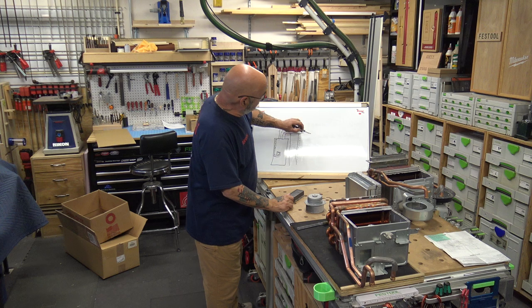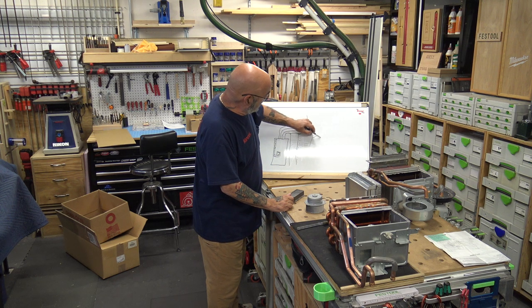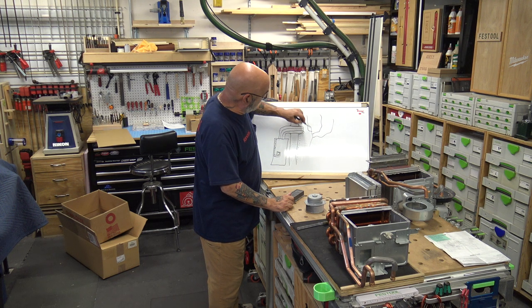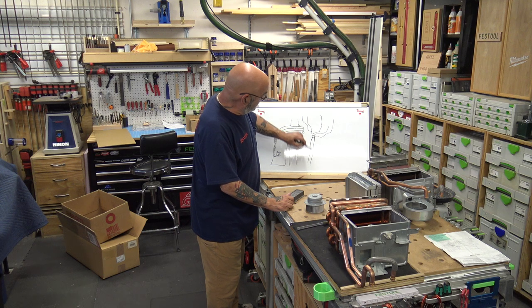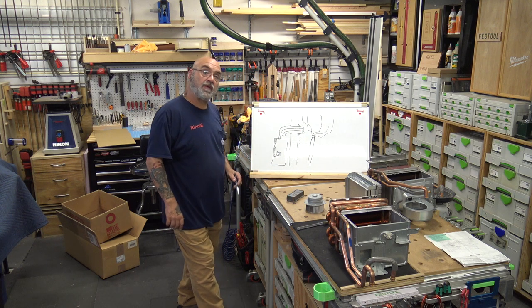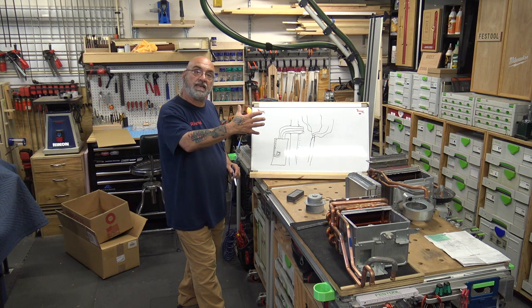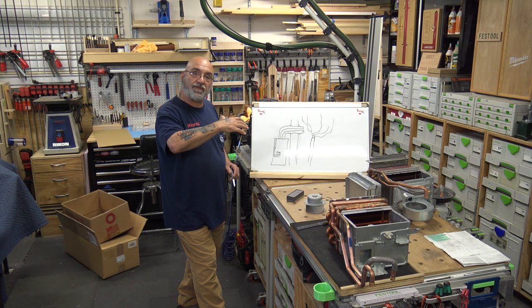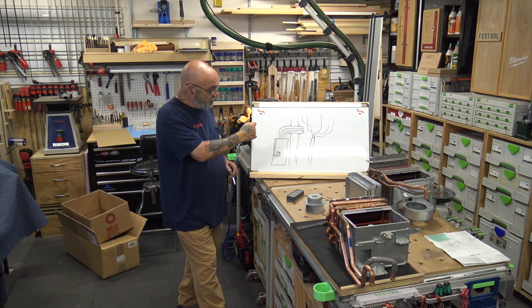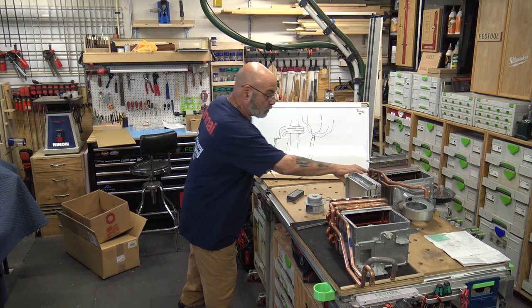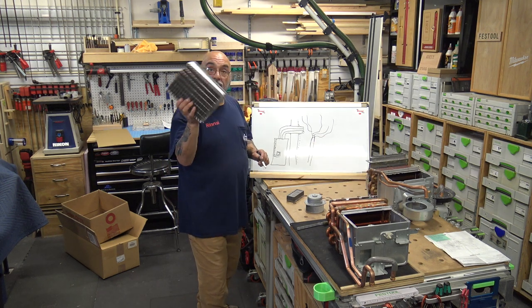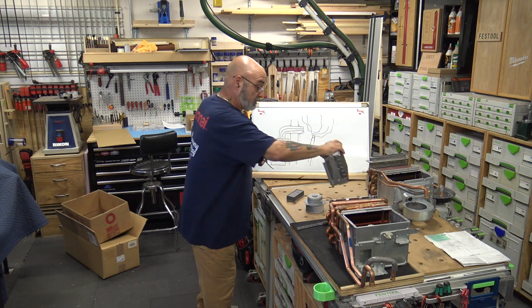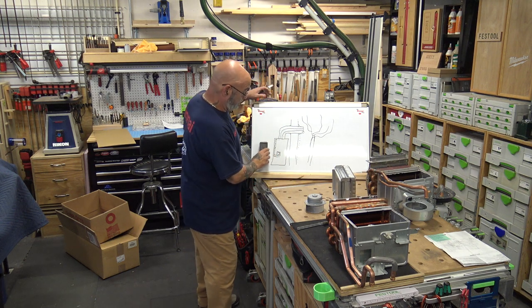If you have a lot of bushes in front, or a tree right there in front of the unit, it's going to suck in all of that dust and debris off of that tree into the unit, and that's what's most likely going to clog up the burner ports and give you that code.